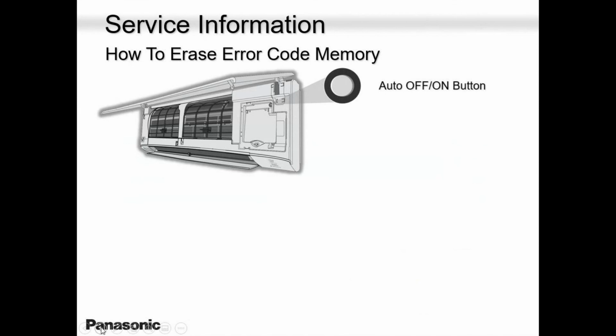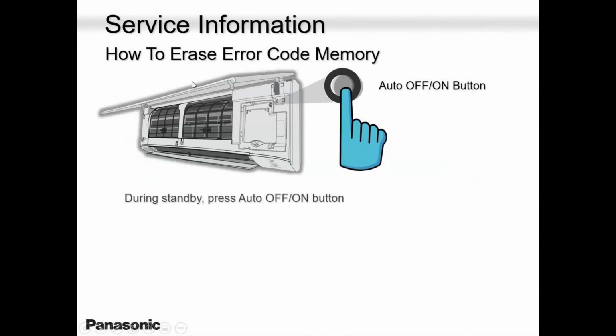Sometimes people will call me and they say, I got this error code. What is the unit doing? Oh, the unit is working fine. So what happened? How did you get this? Oh, I was on a service call. I was on a maintenance call and I decided to pull this. So guys, you're pulling wrong errors. The errors that were there before that got rectified or repaired. So only do this when the timer light is flashing.